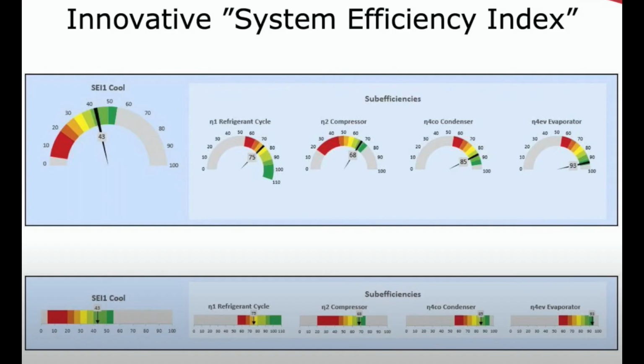Well, this system compares what's actually being carried out or delivered by the chiller at any moment in time to the perfect Carnot cycle. With that we can see how efficient the chiller is working, even in light load or low ambient conditions, etc. The other four dials shown there: one shows the performance of the actual refrigeration cycle, another the actual compressor and the efficiency it is working at, the condenser, and then at the right side, the evaporator.